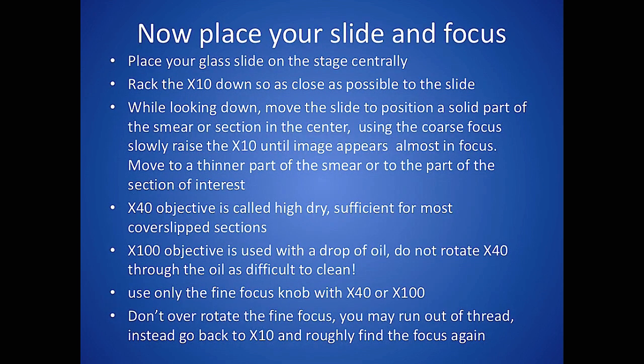Now grab your slide and let's focus. Place your slide centrally, bring your 10x objective down as close as possible — remembering it won't smash the slide — then find a solid part of your section or smear and use the coarse focus to sharpen the image. Then move to a thinner part of the smear; as a microbiologist, I look for a thin part of the section so I can see individual microorganisms.